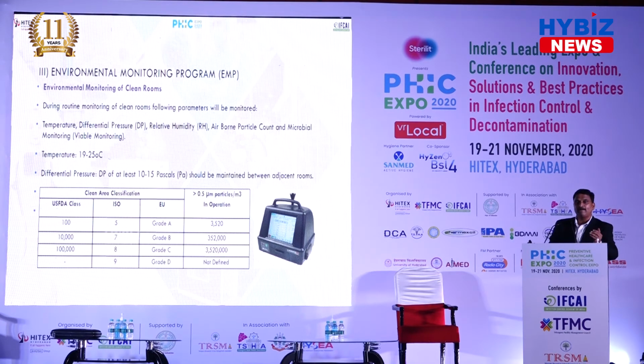For some products, there are specific relative humidity requirements. For example, take amoxicillin potassium clavulanate, an antibiotic. Clavulanate potassium requires an RH of 25%. There, a specially designed clean room for RH should be provided. However, the RH for regular general clean rooms is 55 plus or minus 5. For some products, there is a specific requirement.